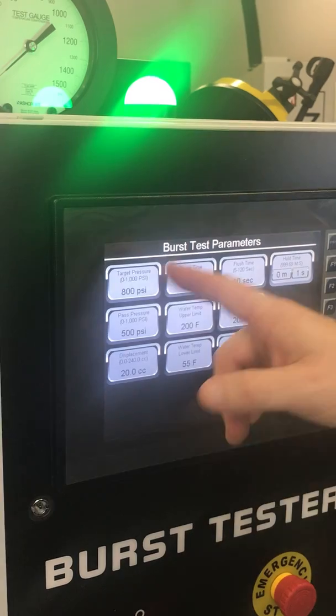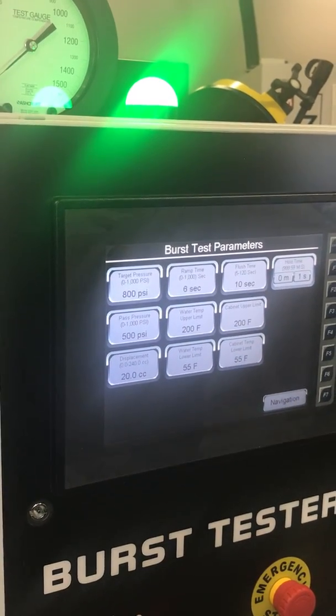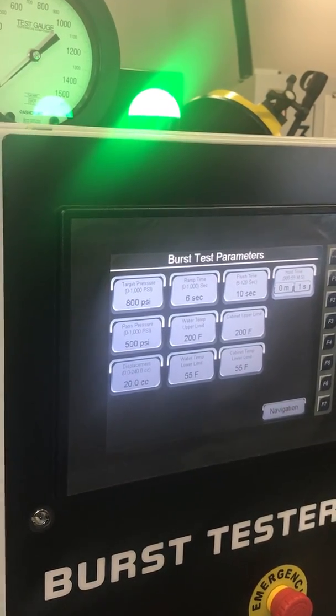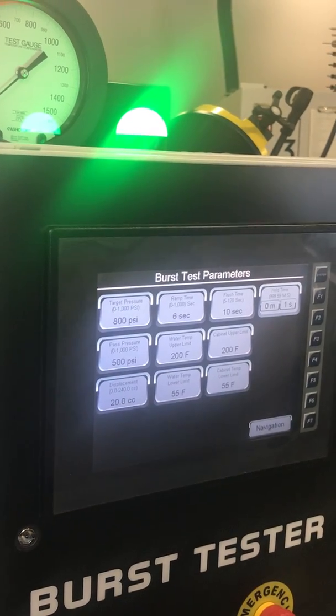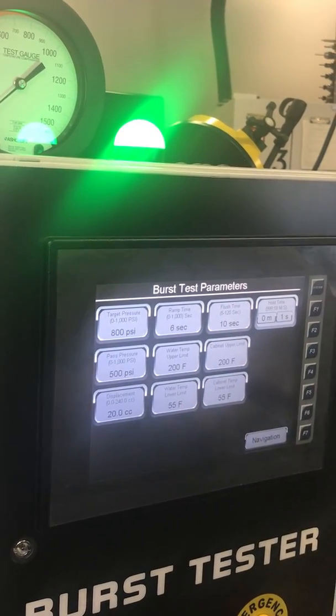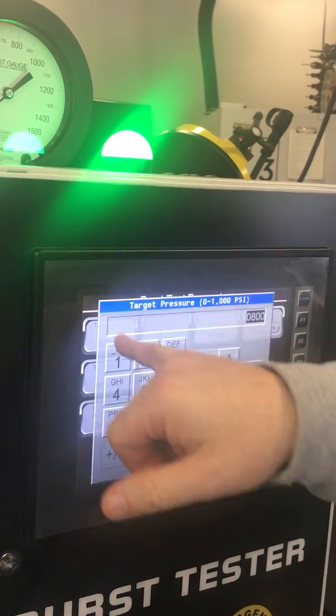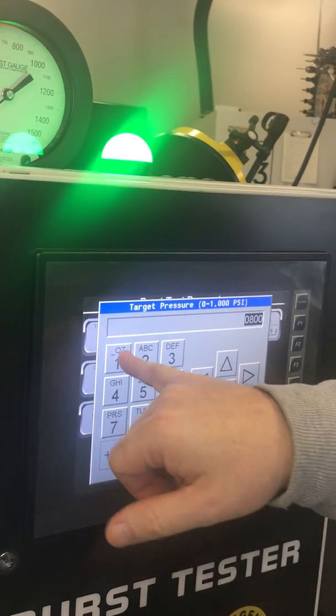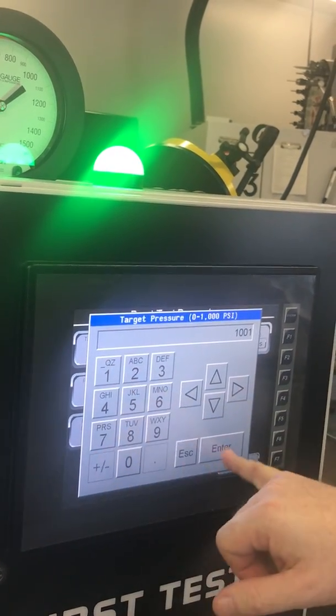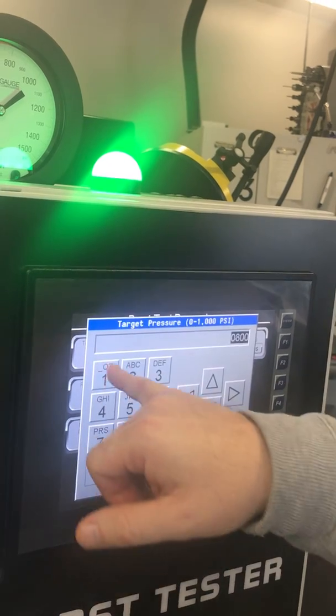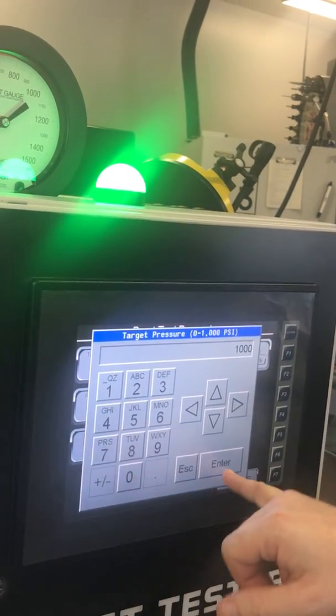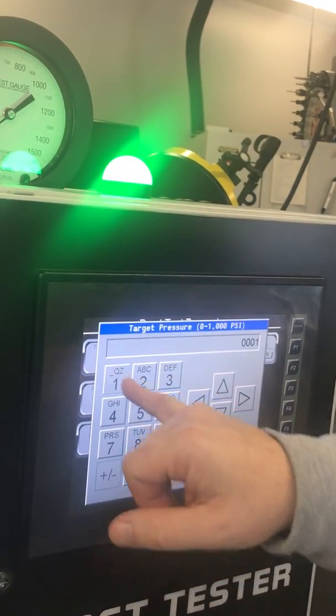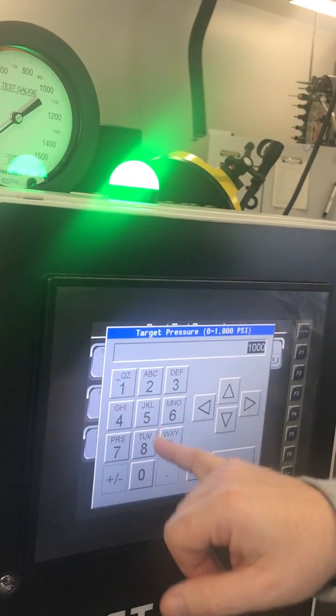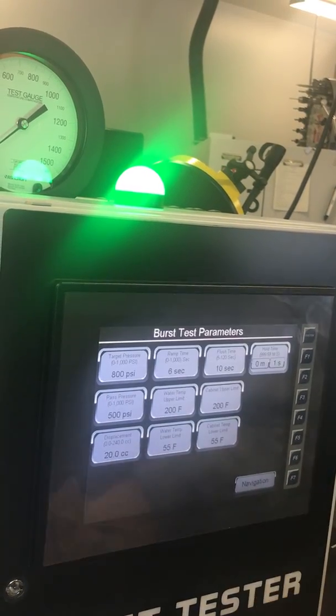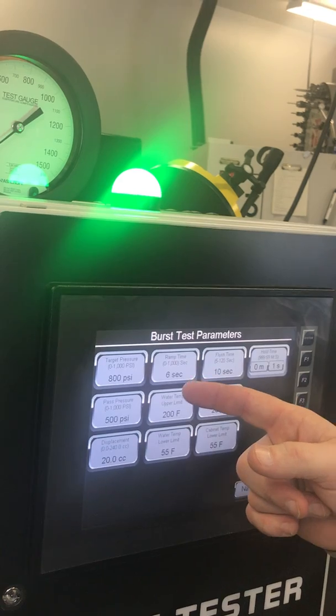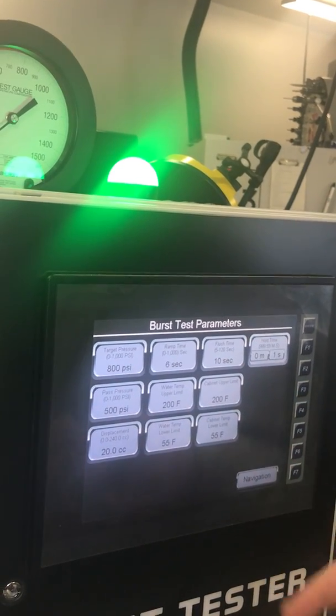Burst parameters. In here is where we can set all the parameters for your burst test. Target pressure, it's going to go up to 800 psi in 6 seconds. The largest number I think I've got you allowed to set is 1,000. Enter. Oops, 800. Enter. So the number of seconds to get there, you can go 0 to 1,000 seconds.